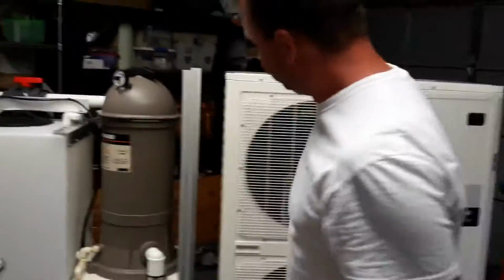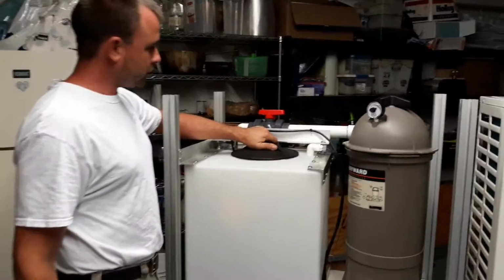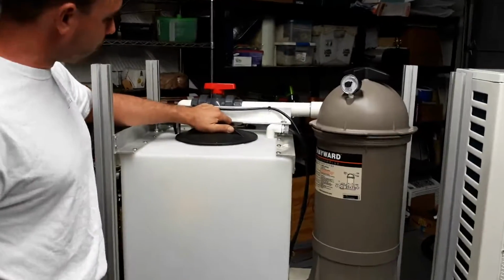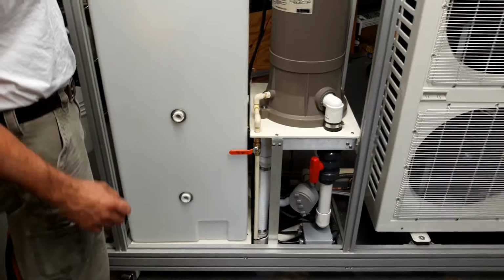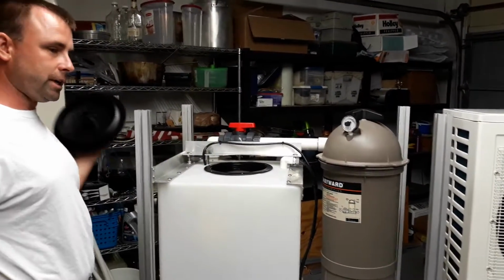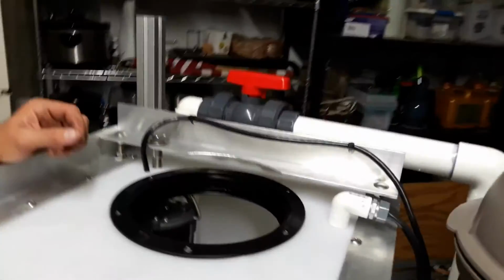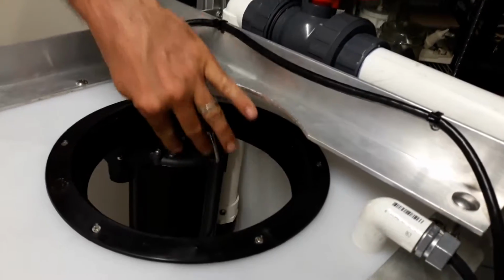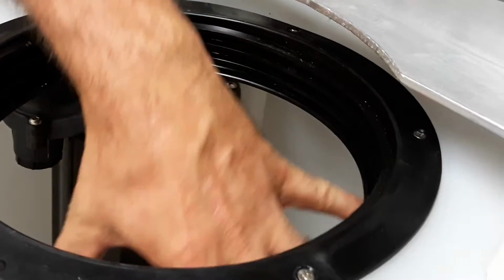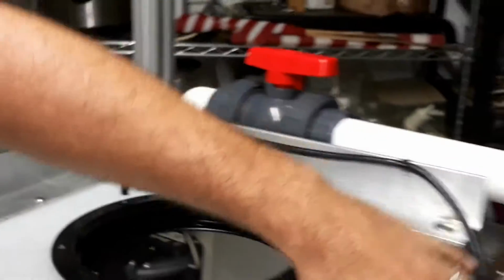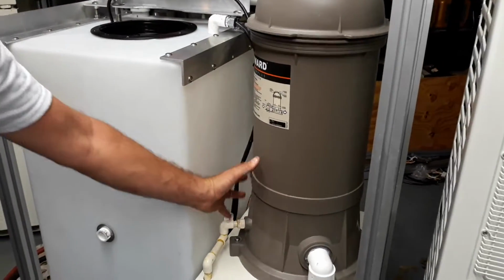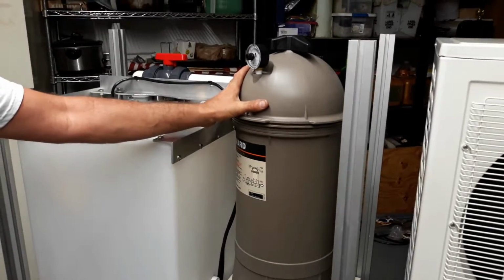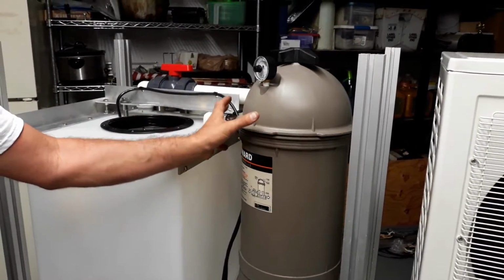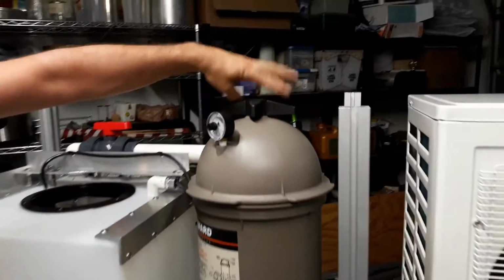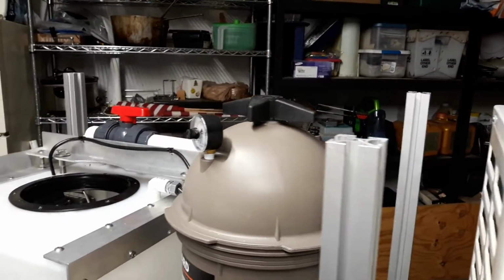Now we move to the business end of it, and over here, this is the access lid to our reservoir tank. This is a 55-gallon reservoir tank. Remove your lid for service, and then there's additional components inside. Inside is a circulation pump, which is drawing water from this tank up through this discharge line into the filter in the rear. This is a pool filter type design with a washable filter cartridge inside, and it's accessed through the top. Remove the cover, extract your filter, and you can wash it.